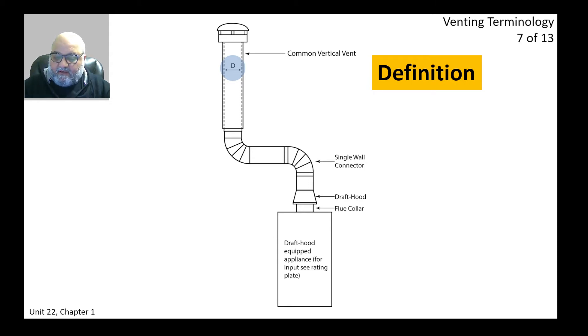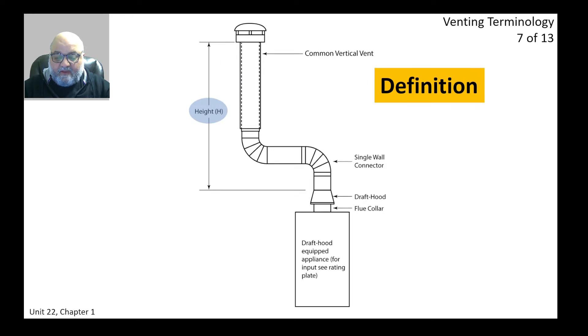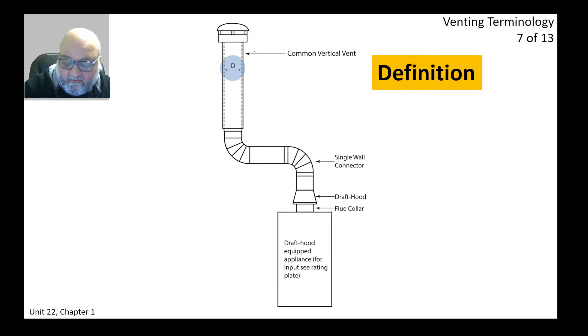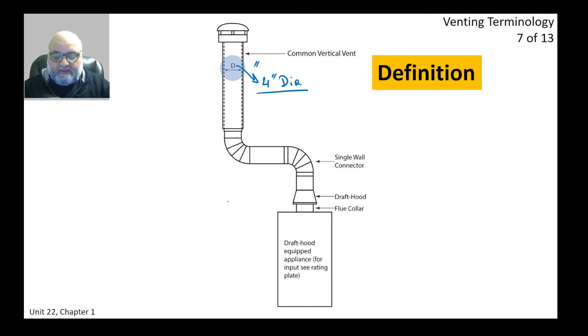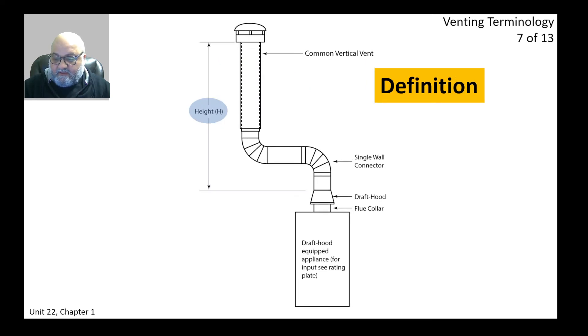Similar to gas piping sizing from last semester, draft is simply a fluid — a gas — flowing in a conduit or pipe. For that we need to know the diameter, which we call the 'size.' Diameter is measured in inches as inside diameter. So if I say four inches in diameter, the inside wall is four inches; the outside wall diameter is typically one inch more, making it five inches.